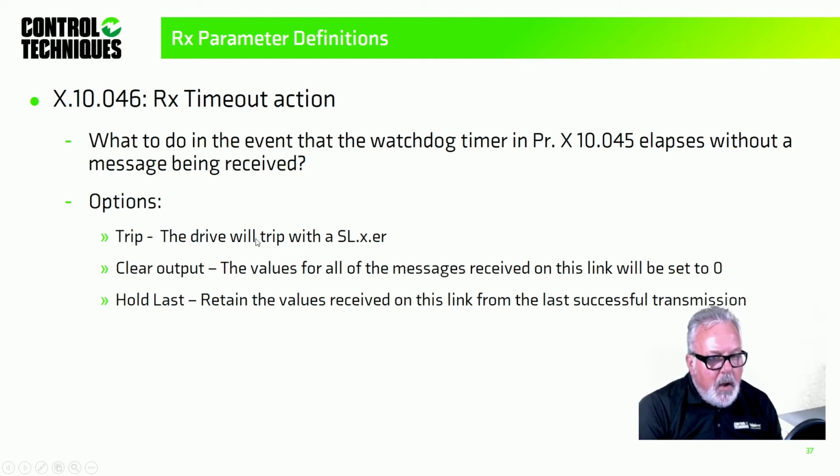If there's something wrong and I'm relying on mission critical data, well, I want to know that that message has not been received or that packet is not being received. So I generally choose to trip the drive if the Watchdog times out.